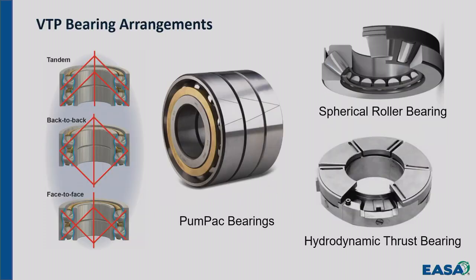The bearing arrangements are a concern. This will usually show up when you install the machine. And it can show up as a bearing failure, it can show up as bearing noise, it can show up as high temperature. There are a lot of different configurations of that thrust bearing on the top of the motor. It could be a single angular contact ball bearing, the simplest configuration. It could be a pair or more, two, three, sometimes as many as four different bearings at the top.